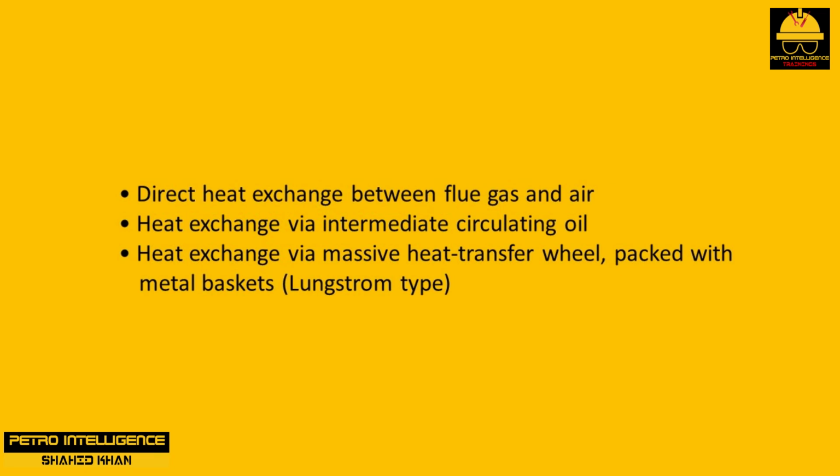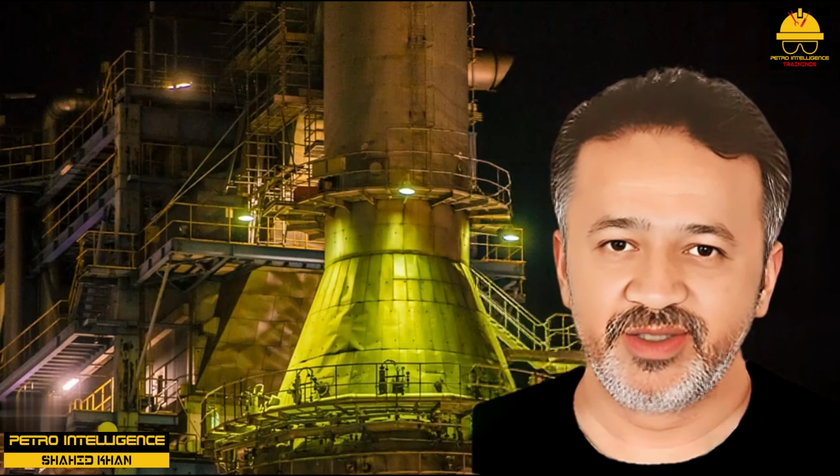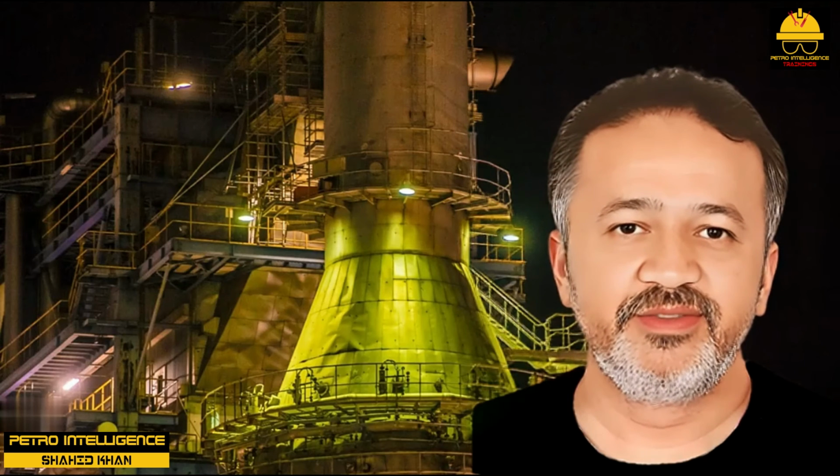Direct heat exchange between flue gas and air. Heat exchange via intermediate circulating oil. Heat exchange via a massive heat transfer wheel packed with metal baskets, Lungstrom type. The wheel type is subject to air leaks across the mechanical seals.